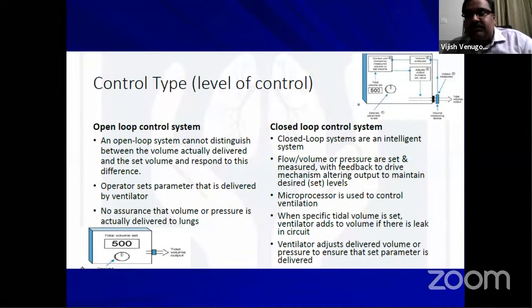So here a microprocessor is used. So when a specific tidal volume is set, the ventilator adds to the volume if there is a leak in the circuit. So the ventilator will adjust the volume or pressure.